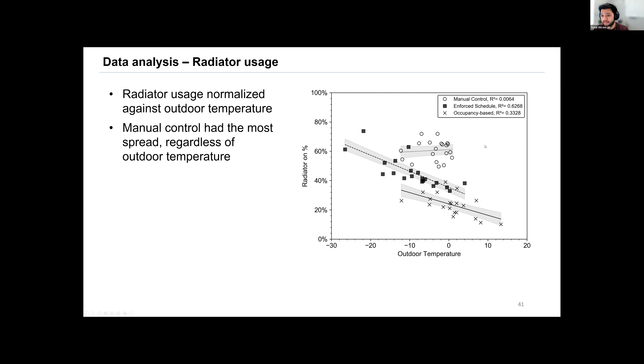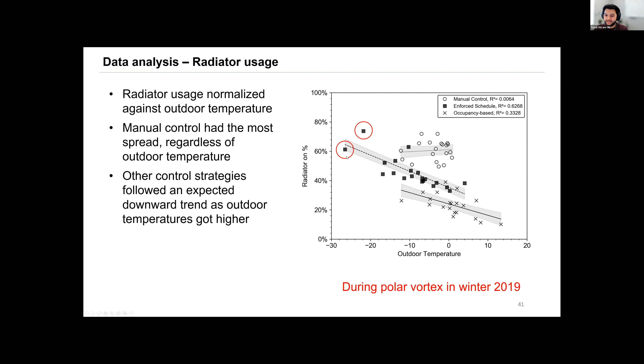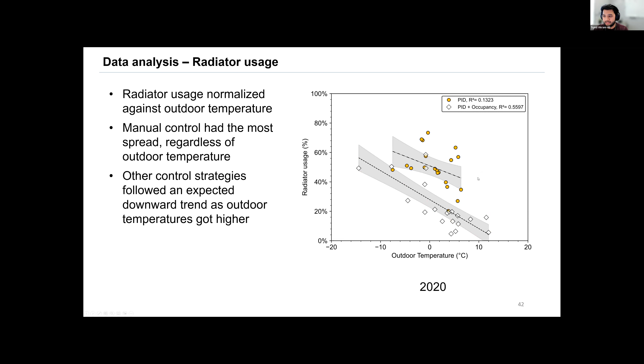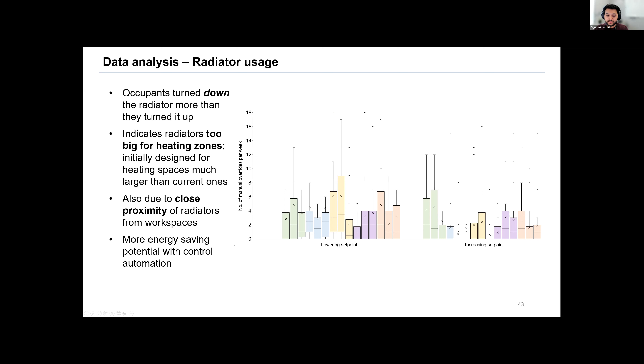The radiator usage barely changes regardless, so clearly manual control or leaving it alone is not a good idea. Other control strategies followed a similar trend. We had some extremities due to the polar vortex in 2019, but we can see that in the data here. All control strategies followed a good downward trend. We also noticed people turned down the radiator more than they turned up, which we saw by logging button presses. This shows that the radiators are too big for the heating zones, because they were designed decades ago and the room layout has changed since then. Clearly legacy systems no longer apply to what we have today, so that's good information to know.